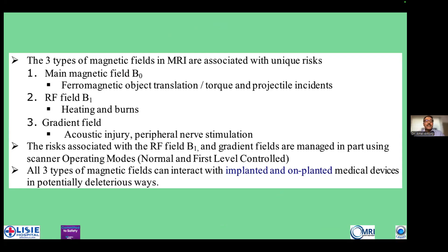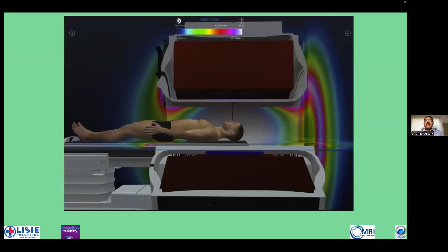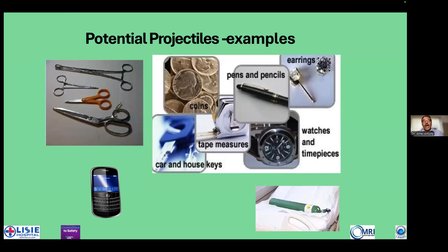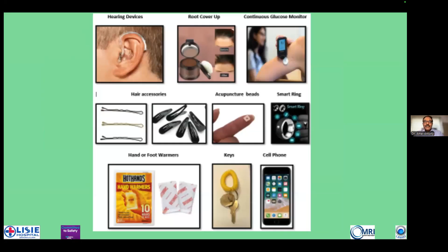Now, when we come to magnetic fields, as shown in this picture, that is the main magnet. You can see that the field is maximum at the ends of this, and any metal can be a potential projectile. So that's why diligent screening is very important to ensure that the patient or the bystander or the medical personnel who enter the MRI suite, including zone 3 and zone 4, are free of any freely mobile projectiles. So a lot of equipment has been pulled into the magnet.